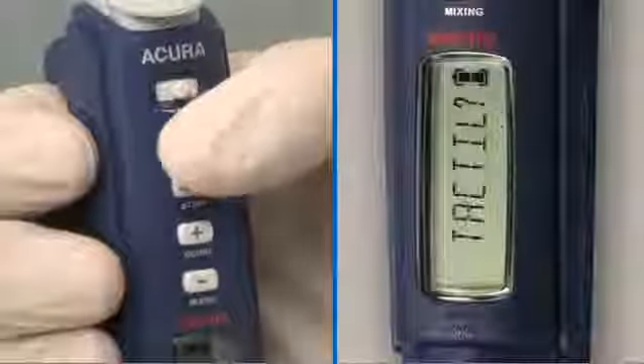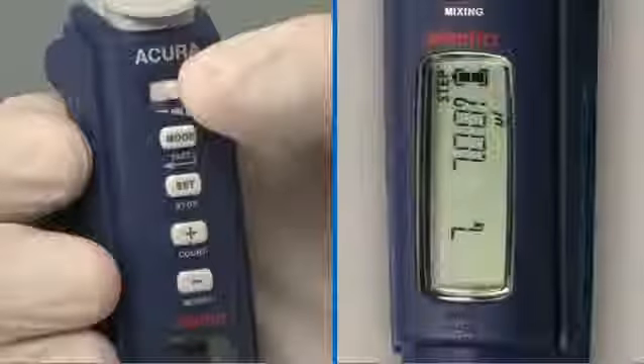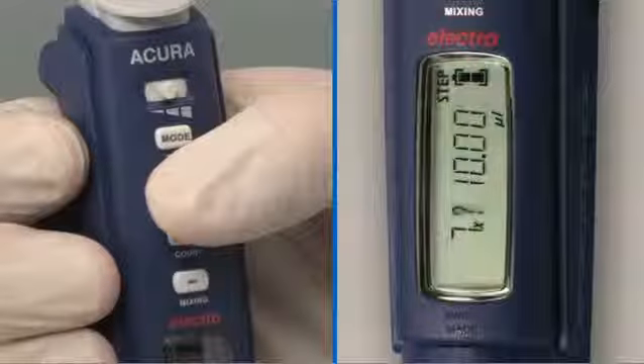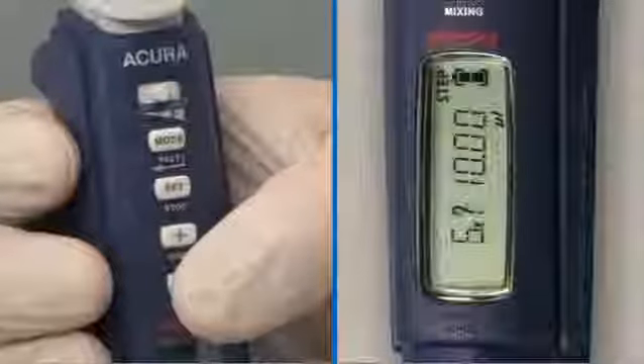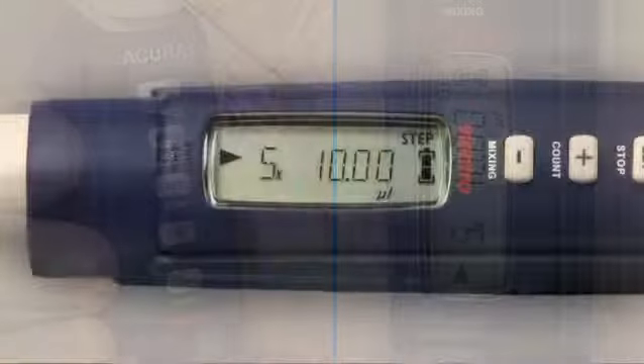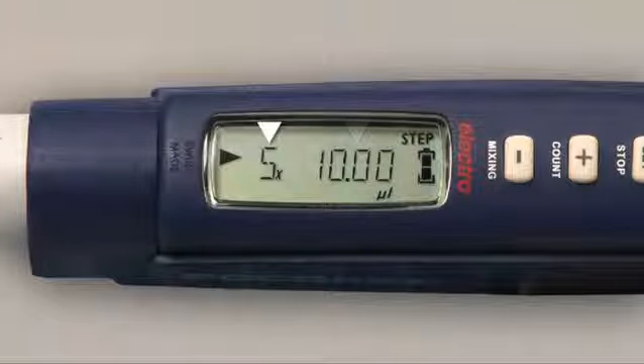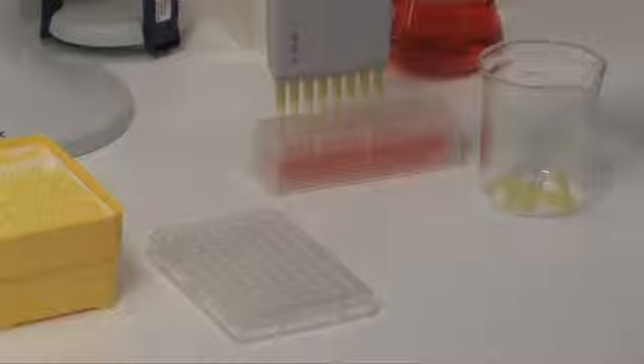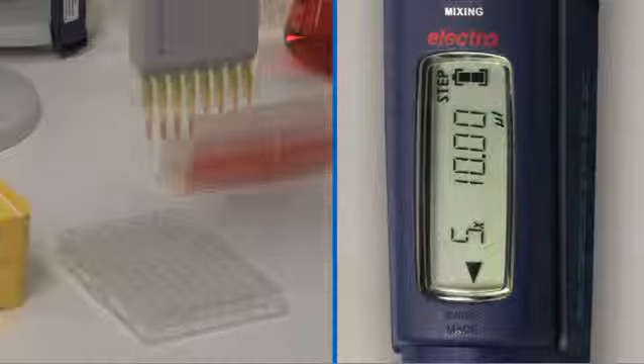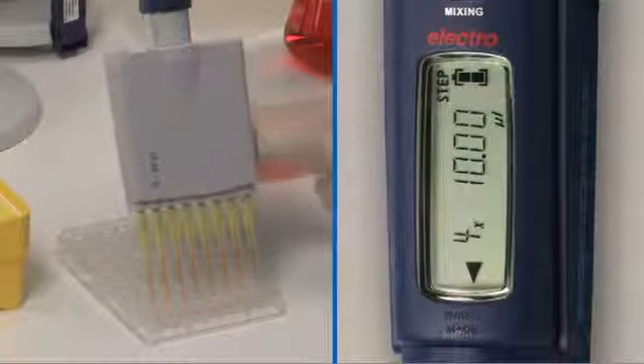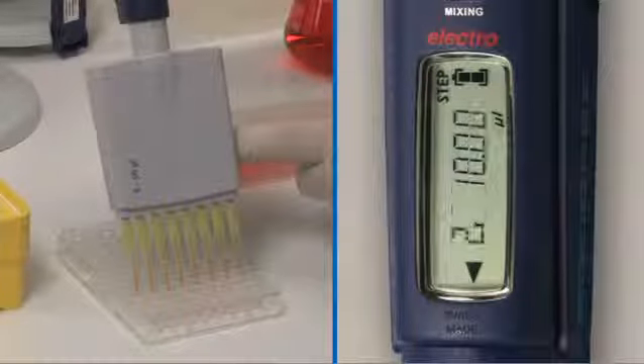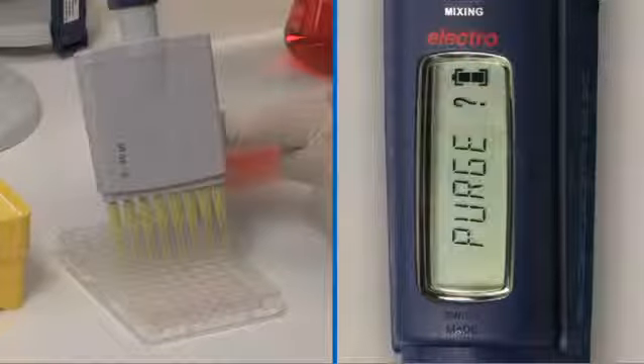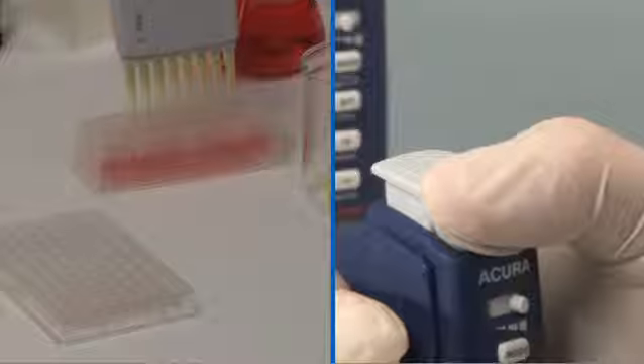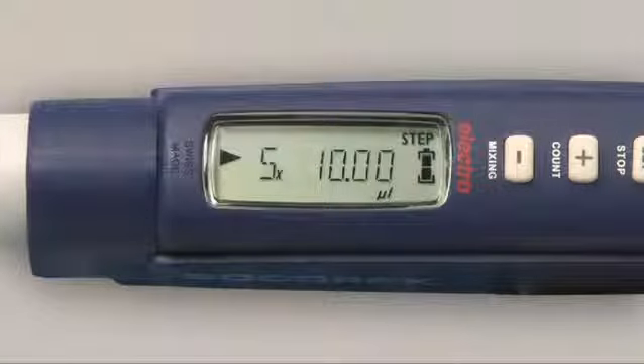Stepper mode enables tip filling and step-by-step distribution. It's best suited to aliquot samples. Press Mode several times until the display shows Step. Press Set to validate. Press the plus/minus keys to display the desired volume for the dosing steps. Press Set to validate. Press the plus/minus keys to display the desired number of steps. Press Set to validate. The display shows the selected mode, volume, and number of distributions. The instrument is ready to work in stepper mode. Aspirate the liquid, and the display shows it's ready to distribute. Each action on the Start button distributes 1 aliquot. After the last dispensing, the display shows Purge. To eliminate the residual liquid, double-click on the Start button. The display shows it's ready to aspirate again.